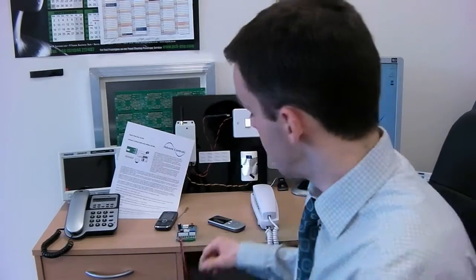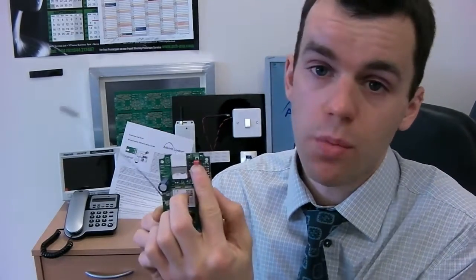Okay, so we can't do anything else without setting up a master number, as they are the only people who are able to make changes to the board. When you get a board new, you'll notice that there's a jumper on there. Just to clarify, as I get asked this a lot, all the jumper can do is allow the master setup text message to be read by the board. Once you've got the first master number set up, you may as well take that off so nobody else can come along and set up a master number on your board. That's all the jumper allows you to do. It doesn't clear anything, it doesn't enable anything else. It just allows that one master text message to operate.